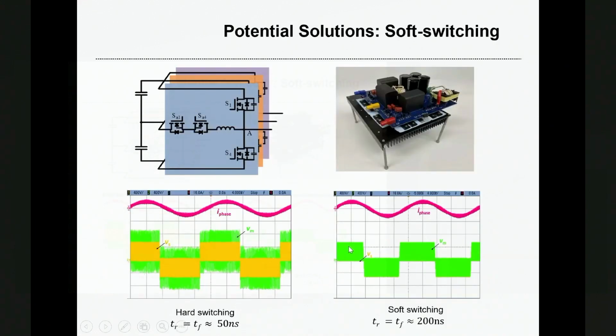And then for the soft switching, we compare it with the hard switching. For the hard switching, the green one is the motor terminal voltage and the yellow one is the inverter output voltage, and motor over voltage occurs here because it's hard switching. For the soft switching, we can shape the switching edge of the output voltage waveform during the transition, and then we can eliminate the voltage overshoot at the motor terminal as shown here.